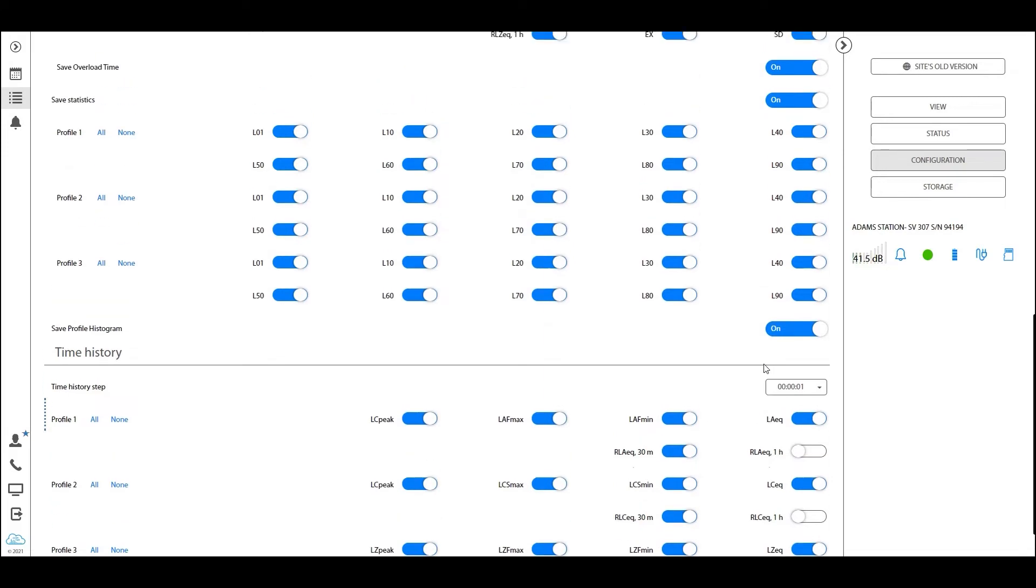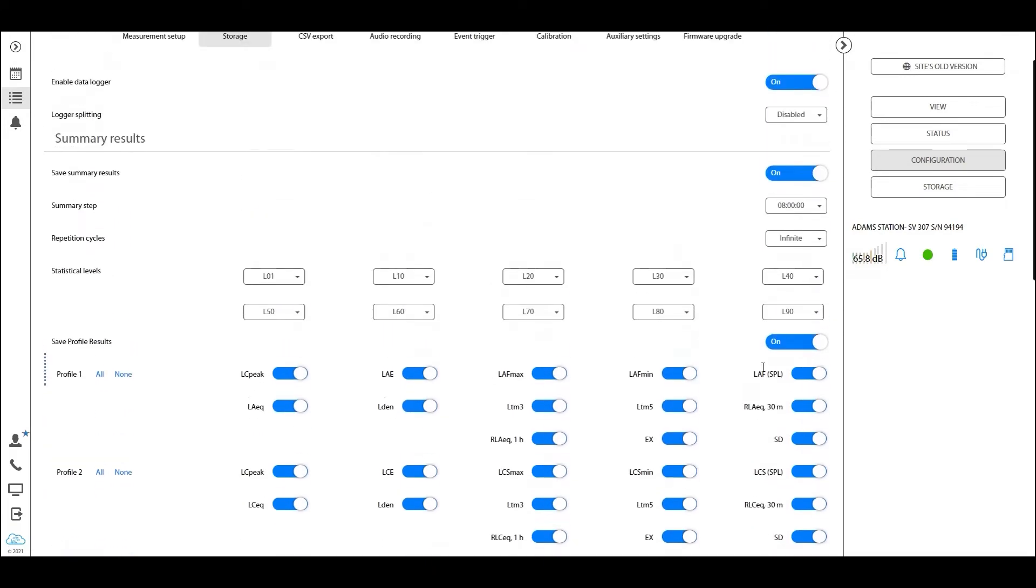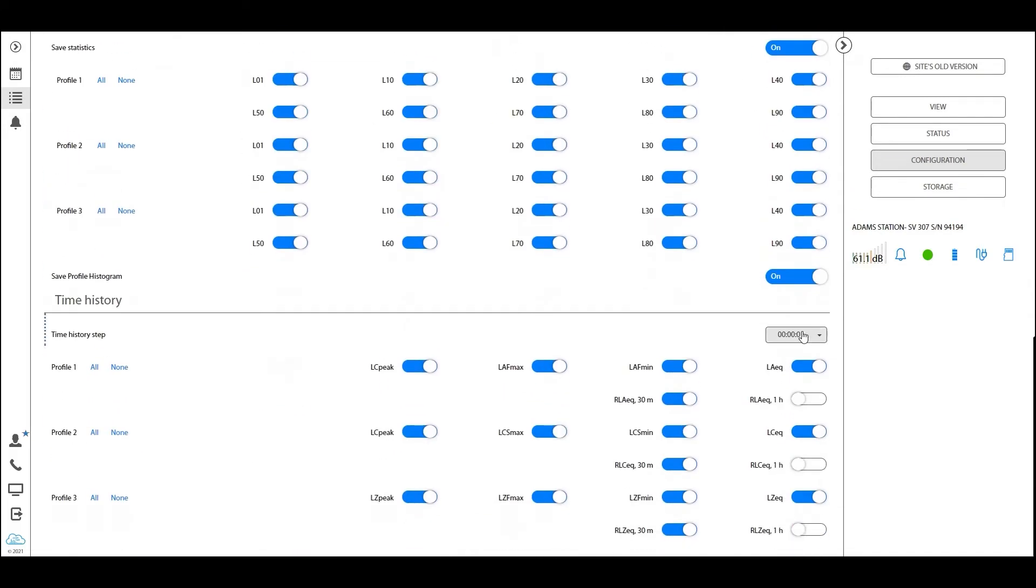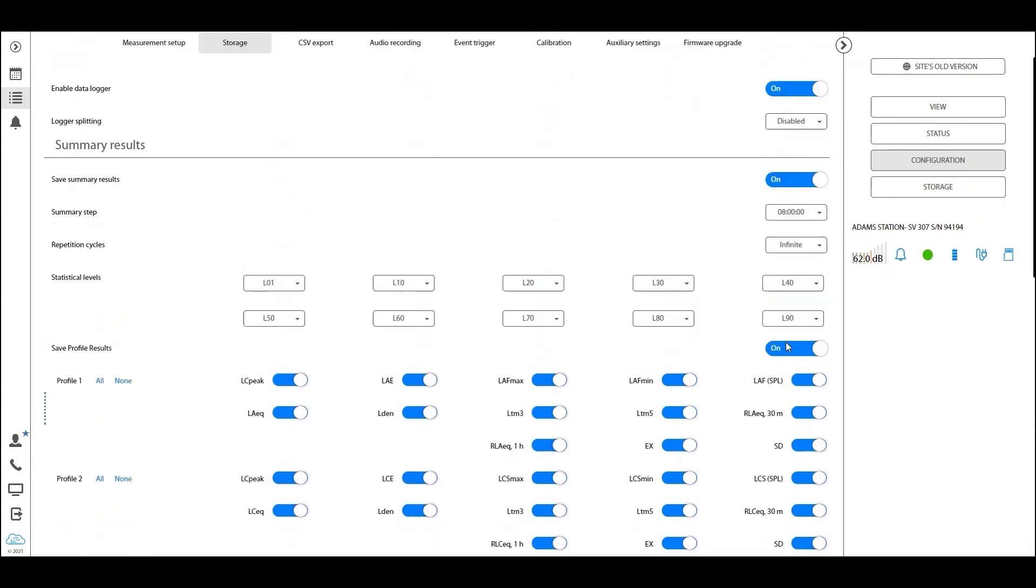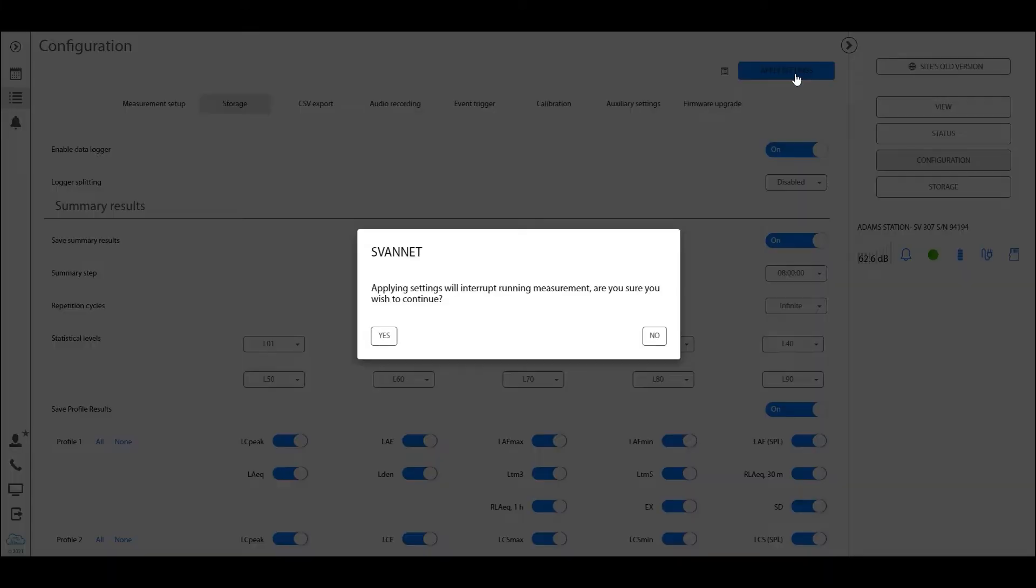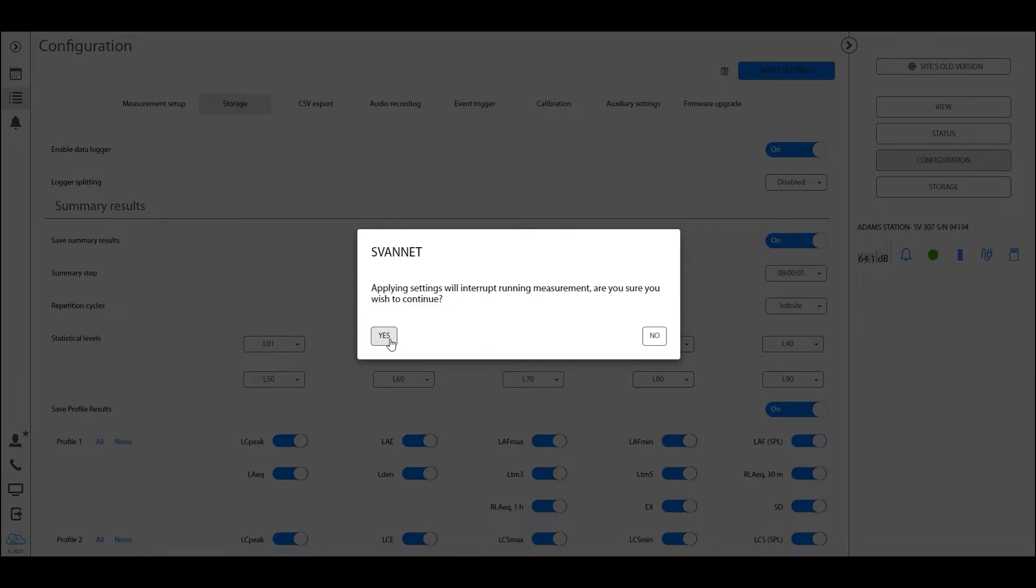Now as you notice, we've made some changes to this configuration. We've set the time history step to one second and the summary results step to eight hours. Now in order for this to go into effect, we must apply settings, and this is what I want to show you in the next step of this tutorial. So hit this button right here. It will ask you to confirm. Remember that uploading new settings to your station will stop the measurement for a short period of time, a couple of seconds, and then restart it. This means that the logger will be split, this means that a measurement will be stopped for a very short period of time.